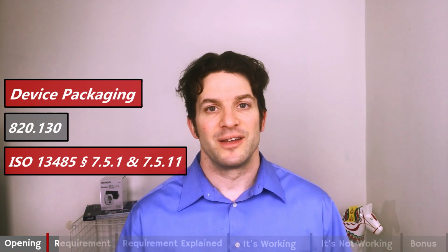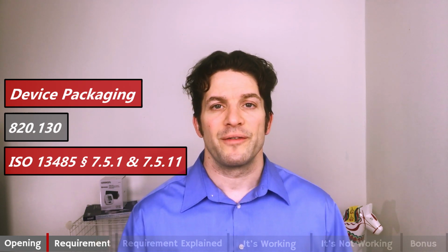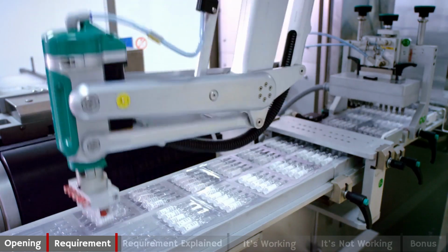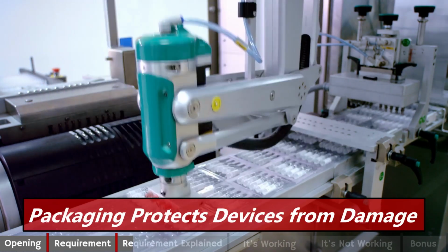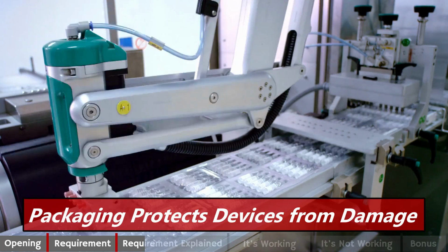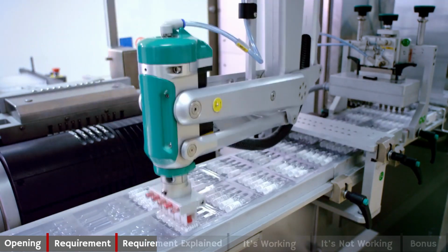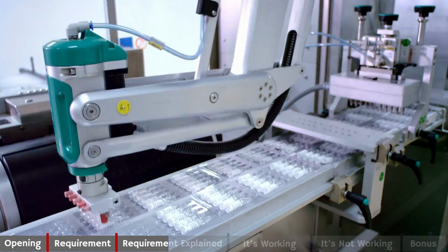Our requirement, device packaging, comes directly from 820.130 and 13485 sections 7.5.1 and 7.5.11. Device packaging in 5 words. Packaging protects devices from damage. We have to ensure that our packaging or our shipping containers protect our product through all handling, storage, distribution, and installation activities. What's important is that packaging itself prevents our product from being damaged.